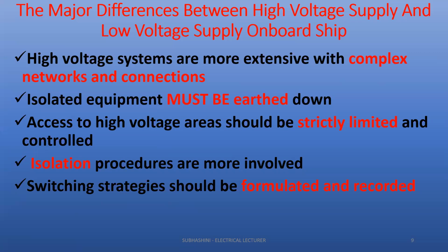Since the capacitance values are increasing, the energy stored will also increase. Even if you put off the power supply, such equipment and cables will have energy stored inside. So it is very much required to earth down the isolated equipment immediately. Whatever voltage is present inside has to be dissipated, discharged immediately. That is why it is given that isolated equipment must be earthed down. Since we are using an HV system, insulation is high and the capacitance value is high. Due to the high capacitance value, energy storage is also high. So that is the reason why we earth down.